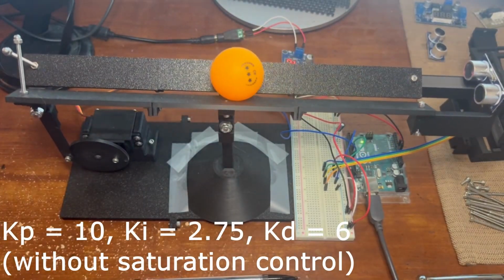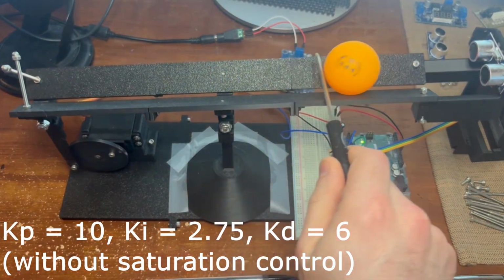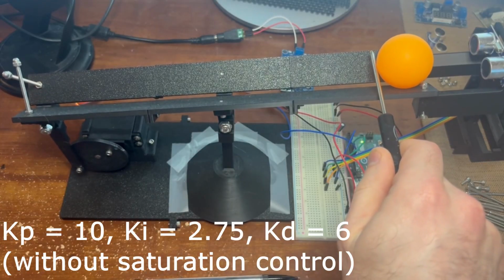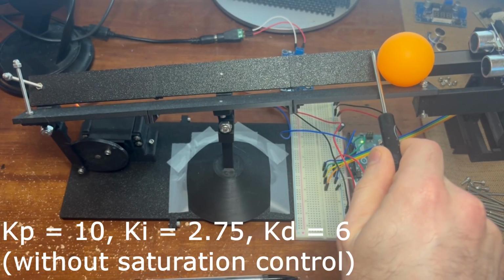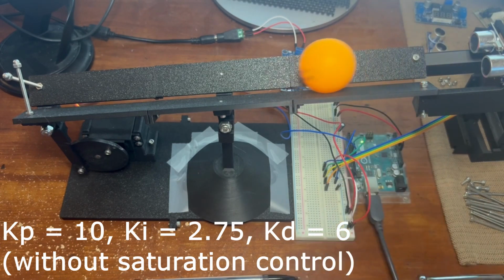And finally, saturation refers to when the controller is operating at its control limits. When this occurs for an extended duration, the integral term can accumulate a significant amount of error and can bias the error in the opposite direction for a long period of time.